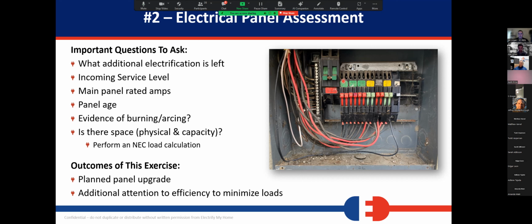So we want to look at what the incoming service level is - obviously that main breaker, can the wire support 125 amps? A lot of times when it's 100 amps, if it's not aluminum, we can support a 125 amp circuit, which helps give us a little breathing room. But whatever the main panel amps are, some of these panels are not rated for 125 amps - the bus bars are only rated for 100.